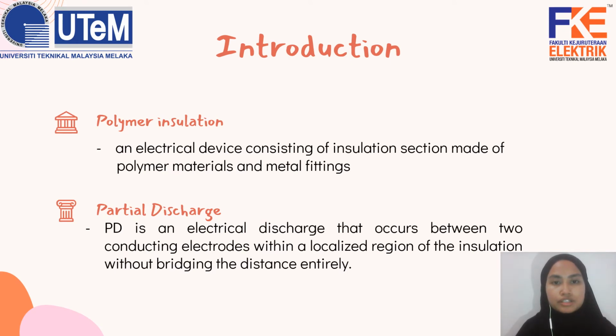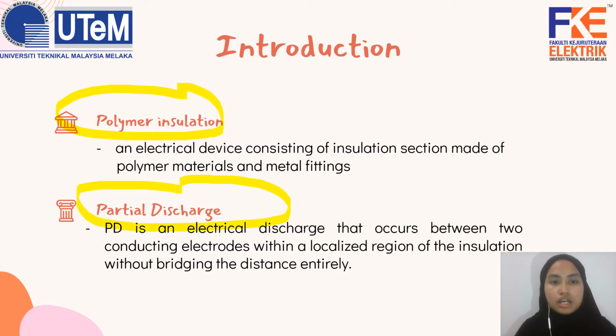This is the introduction of my project. Basically, my project is related to polymer insulation and partial discharge. What is polymer insulation? Polymer insulation is an electrical device consisting of an insulation section made of polymer material and metal fitting, while partial discharge is an electrical discharge that occurs between two conducting electrodes within a localized region of the insulation. The partial discharge process occurs in electrical equipment subjected to high voltage stress. It represents the dielectric breakdown of an electrical insulation.